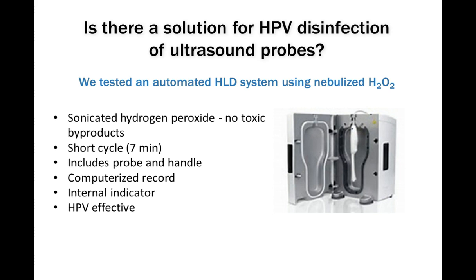So this left us with nothing to use, basically. So we had a question, is there a solution for this HPV disinfection of ultrasound probes? That's when we started to study this automated high-level disinfection system that uses nebulized hydrogen peroxide. So there's sonicated hydrogen peroxide, which means there's no toxic byproducts. There's a short cycle of 7 minutes. The actual contact time is more like 2 minutes, but the full cycle for the machine is 7 minutes.